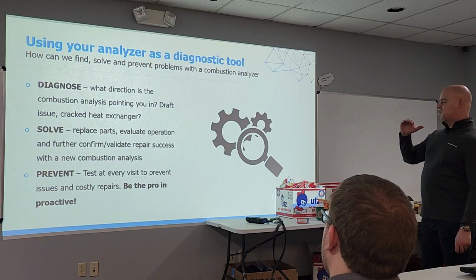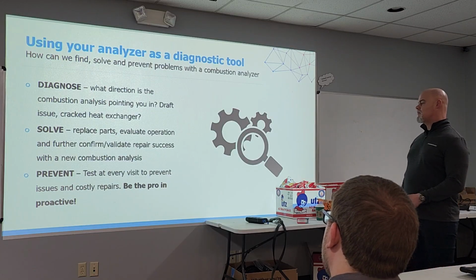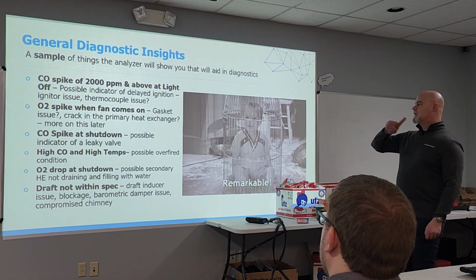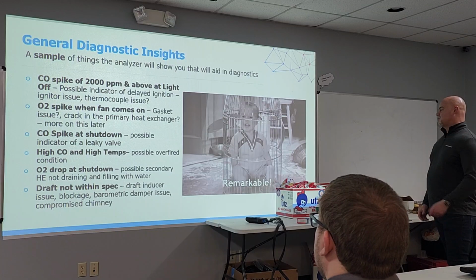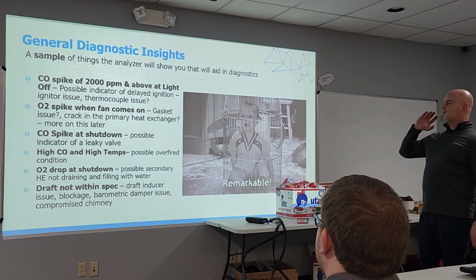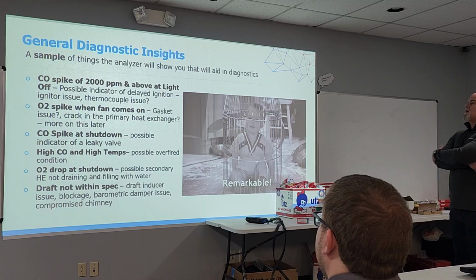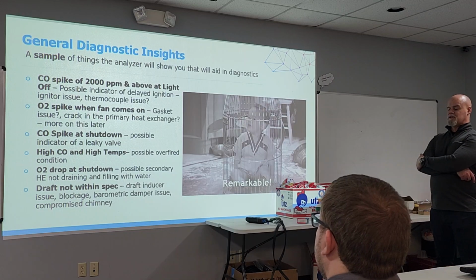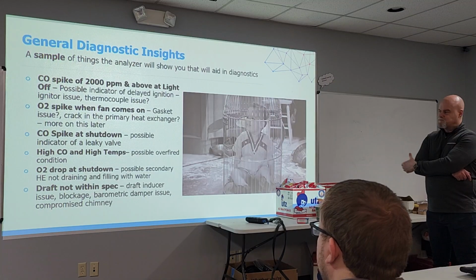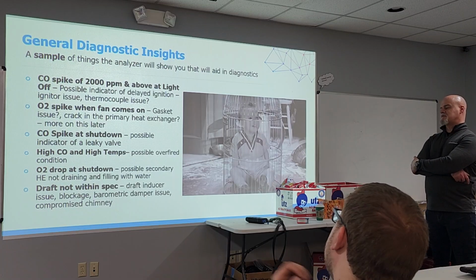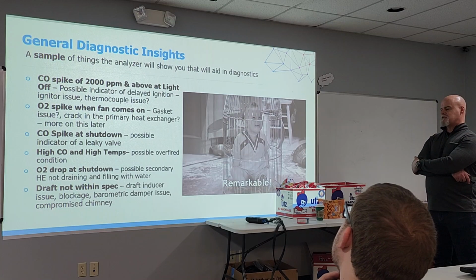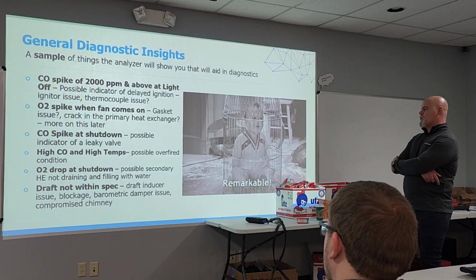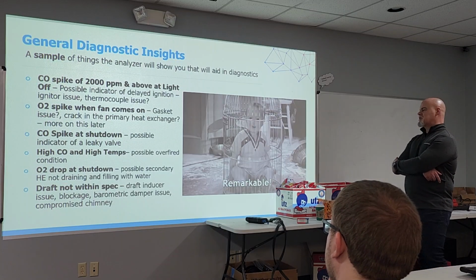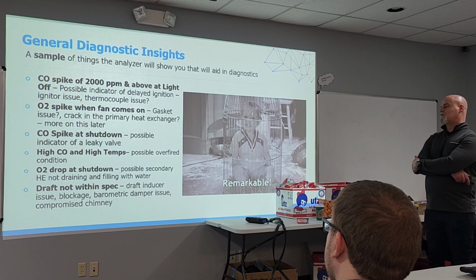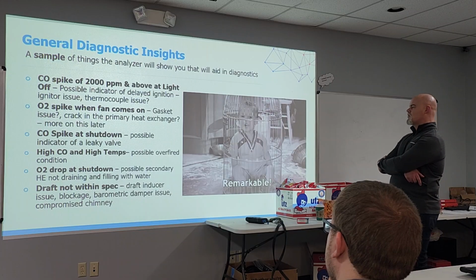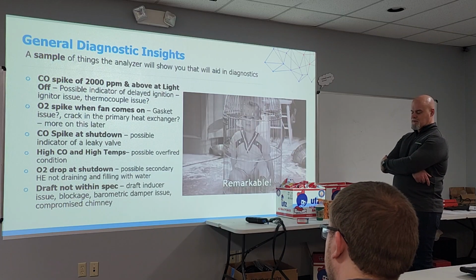And then you're gonna prevent. You're gonna test it every visit to prevent issues and costly repairs. Be the pro and proactive. General diagnostic insights, which he just thinks is remarkable. CO spike at 2000 ppm and above at light off: possible indicator of delayed ignition, igniter issue, thermocouple issue. O2 spike when the fan comes on: possible indication of a cracked heat exchanger, gasket issue. We're gonna talk more about that later. CO spike at shutdown: possible indicator of a leaky valve. High CO and high temps: possible overfire condition. O2 drop at shutdown.